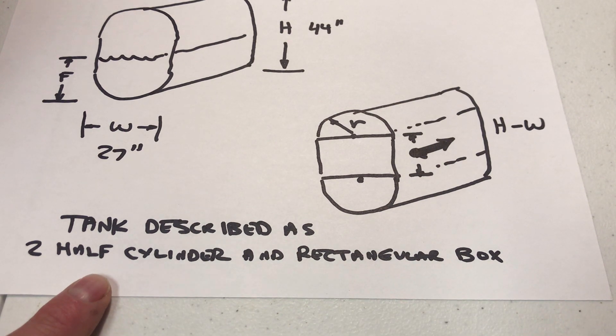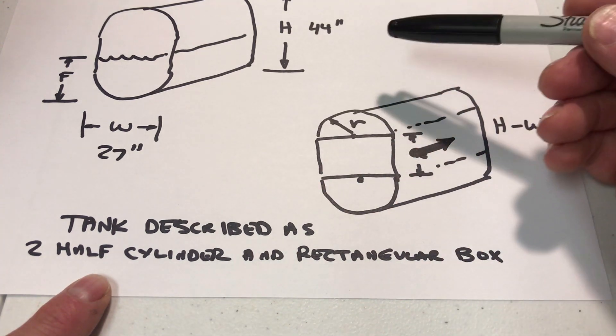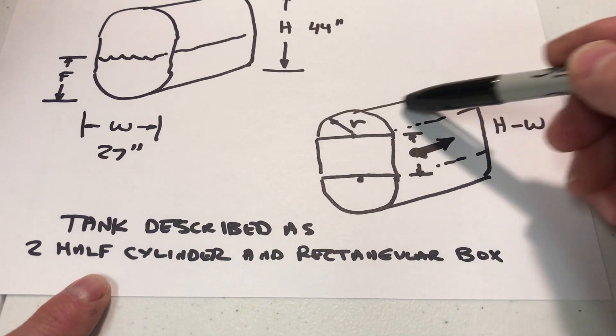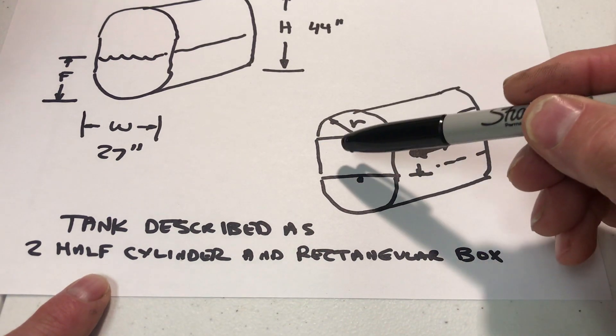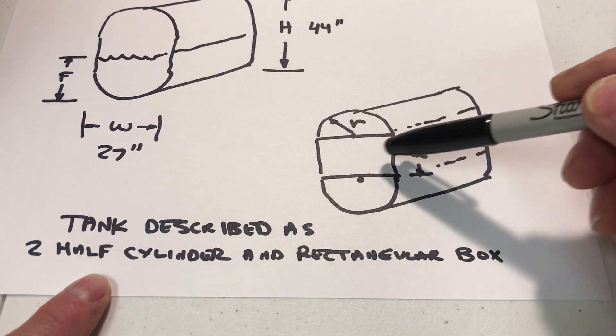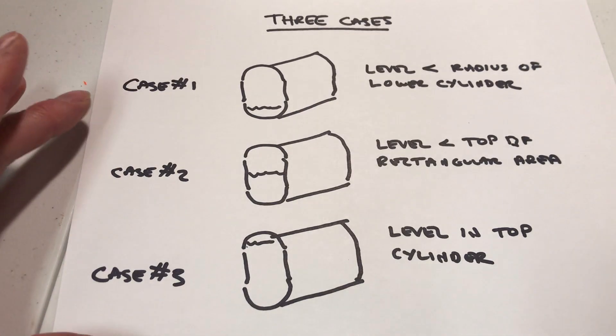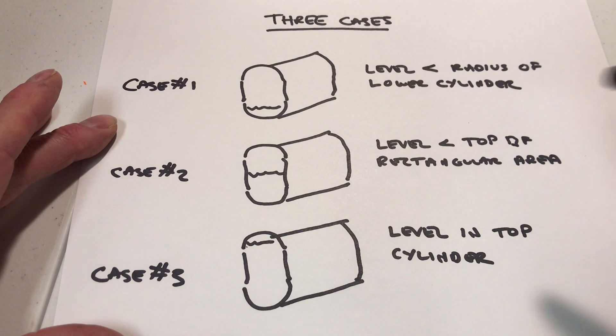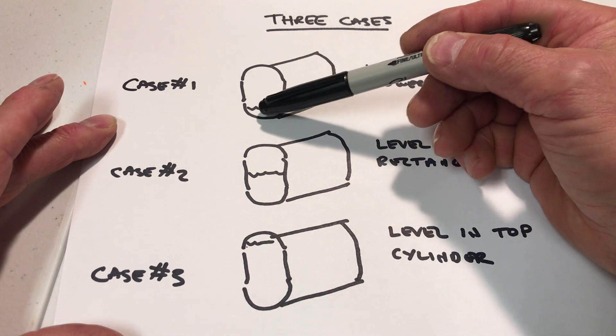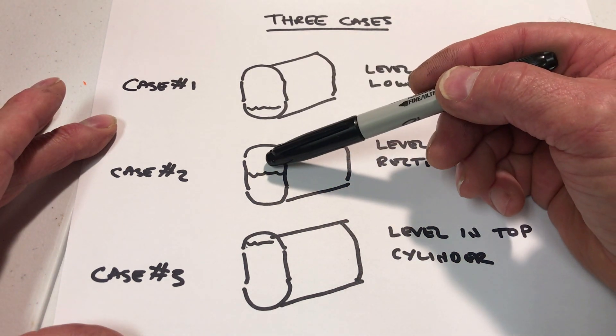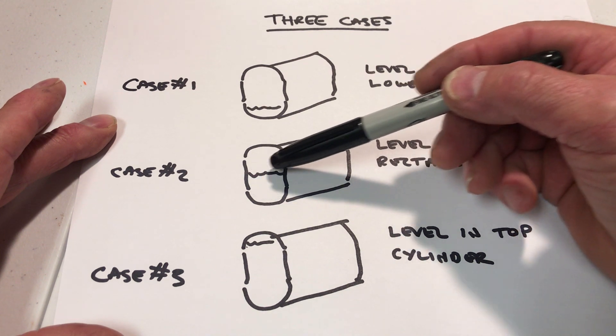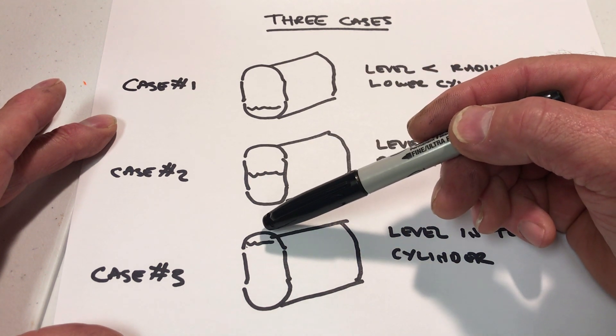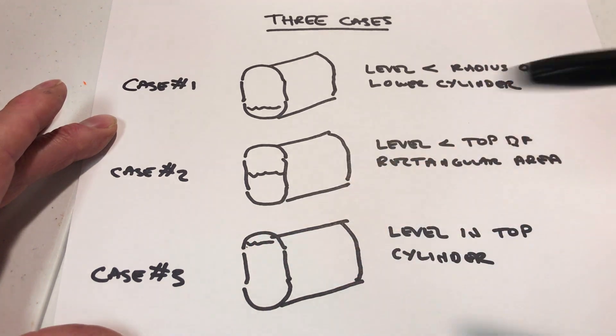To solve the equations, it's easier if you think of this tank as really two half cylinders—one on top and one on bottom—and then a rectangular area in the middle. Then you just have to think of the problem in three different cases: one where the level is in the lower cylinder, one is when it's inside the rectangular area, and one is when it's in the top cylinder.